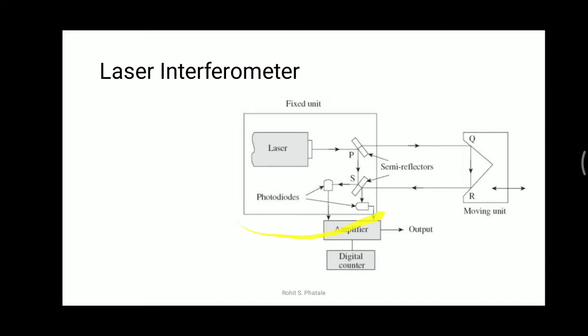There is a fixed unit and a moving unit. The moving unit is a cube — a rectangular block cut into a triangular shape — known as the corner cube. A number of semi-reflectors and photo diodes are installed, and two inputs are given to an amplifier which provides a digital output.